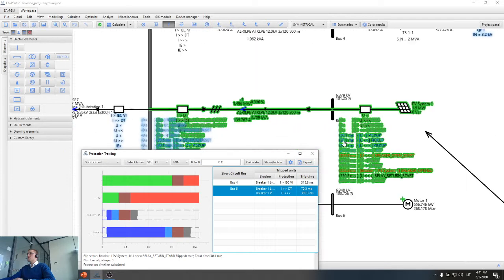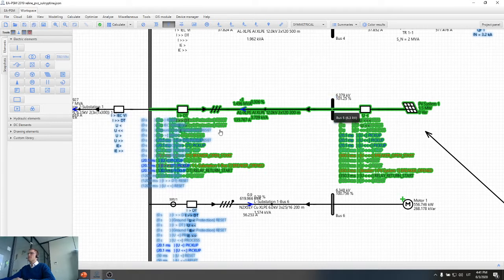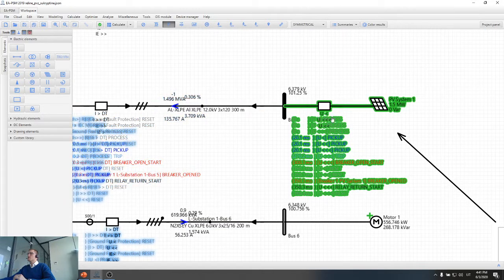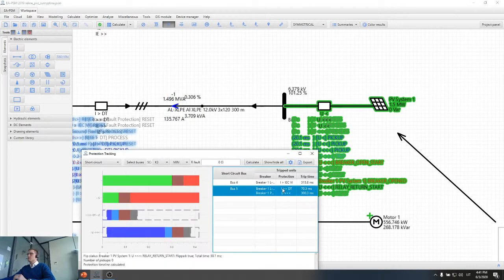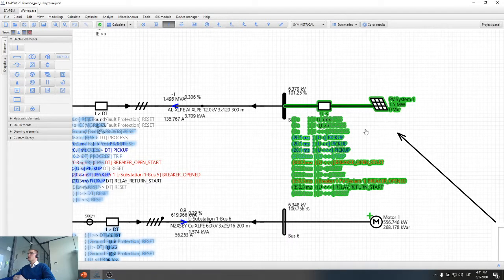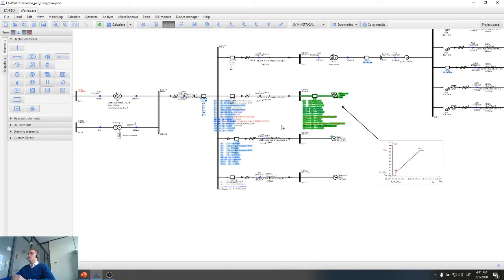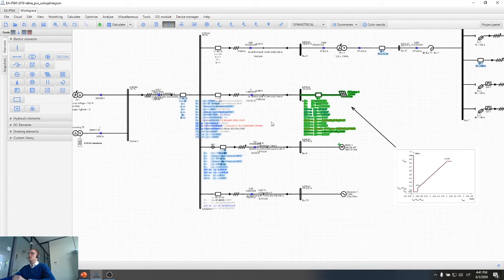In case of bus 5 short circuit, bus 5 is basically here in between the solar power plant and the main bus bar. So 2 protection devices have tripped. First of all, the overcurrent protection device on the line here has tripped, and later on the voltage protection device which is protecting the solar PV plant has tripped. So the operation, as we can see, is first overcurrent protection device, and after 300 milliseconds under voltage protection device. So this protected the power system from working into a bus bar which is not connected to the network.